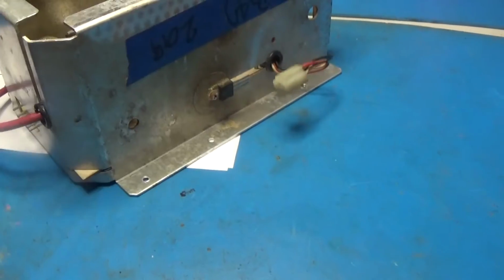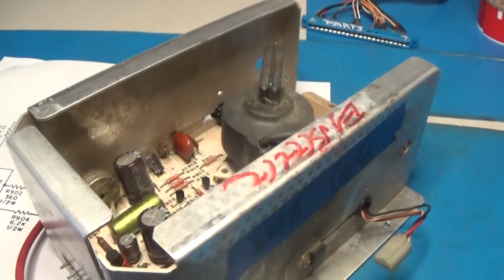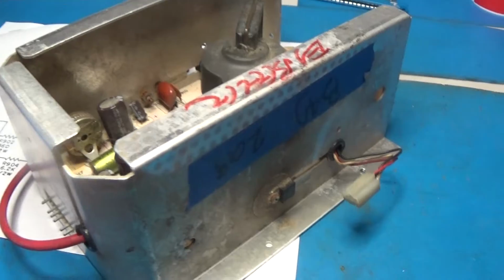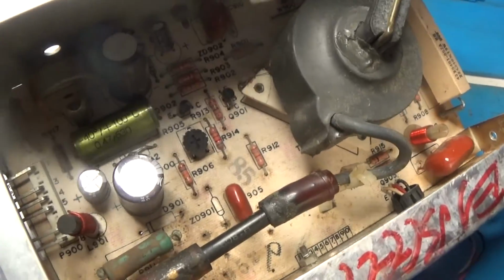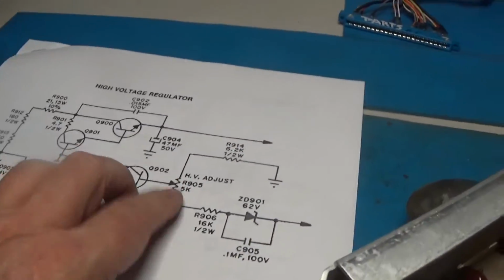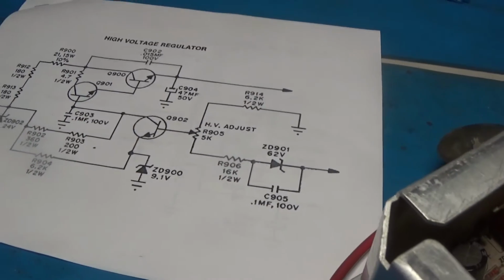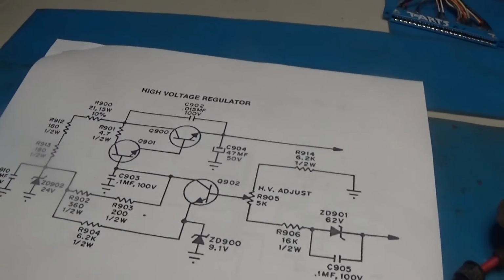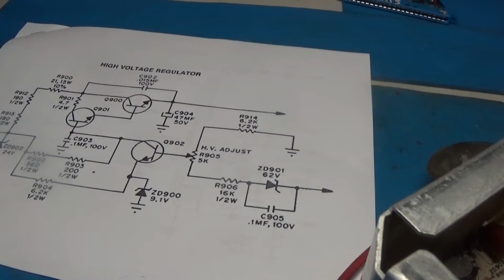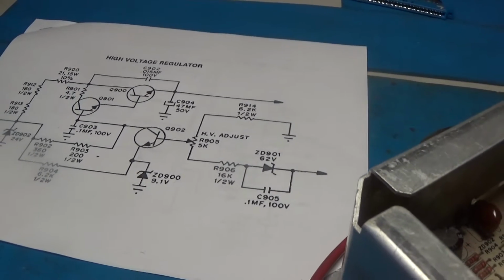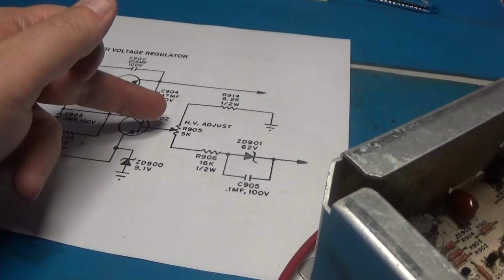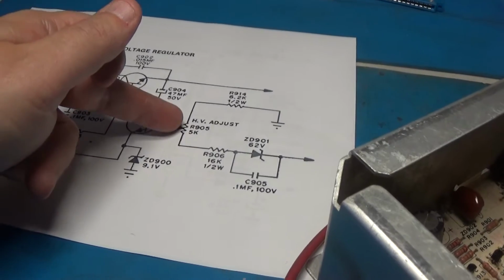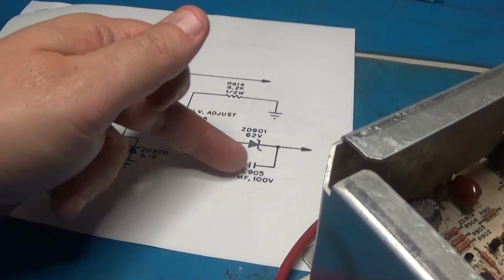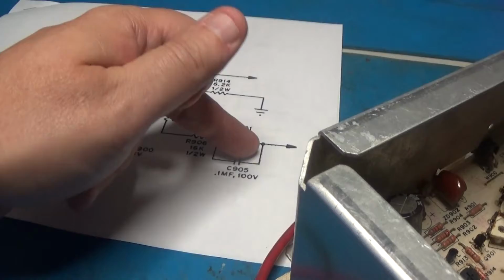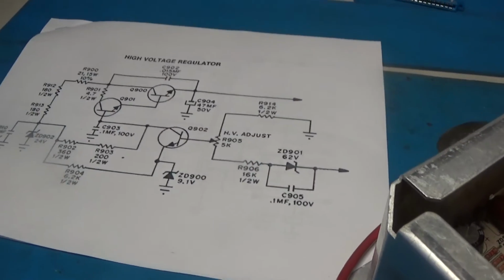Yeah, so we'll hook it back up and see if it makes a difference now that we've got regulation on the high voltage. Because we didn't have any, that pot was bad, and that's in the regulation circuit. So, the high voltage regulator. That could have been the whole problem. And if we weren't getting anything from wiper to down here, that would maybe explain the 0 volt situation that we had. I don't know. We'll see.